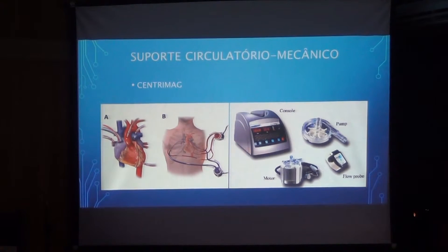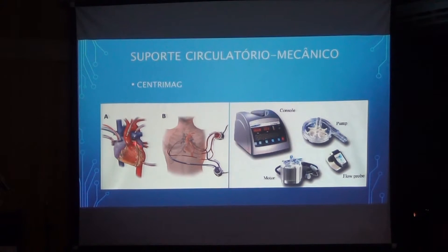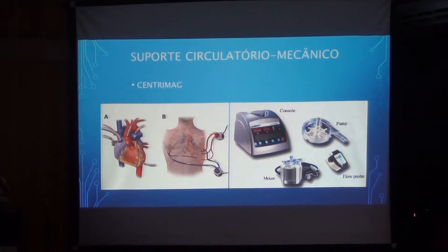The Centrimag is a centrifugal pump that works similarly: you take the flow from a vein or the right side and return it to the other side. This pump provides left-sided ventricular assistance, and you can control the rotation — and therefore the degree of assistance it provides.